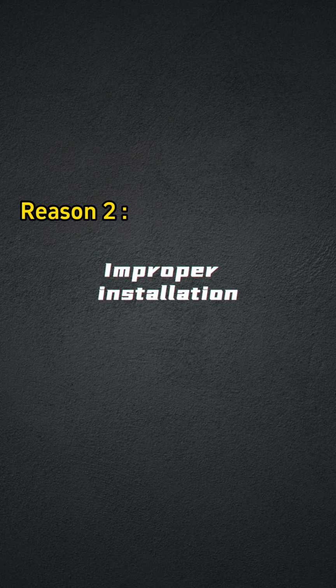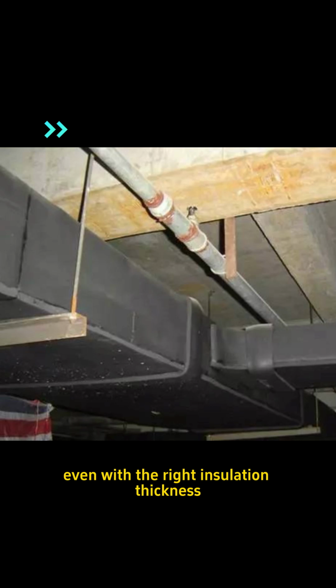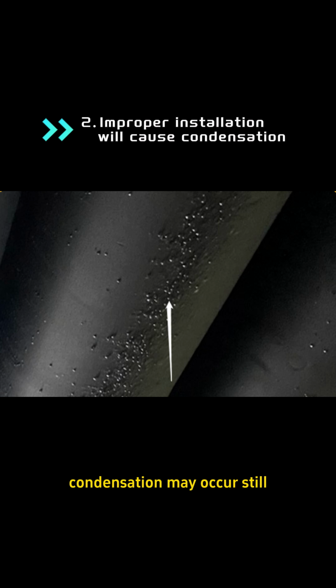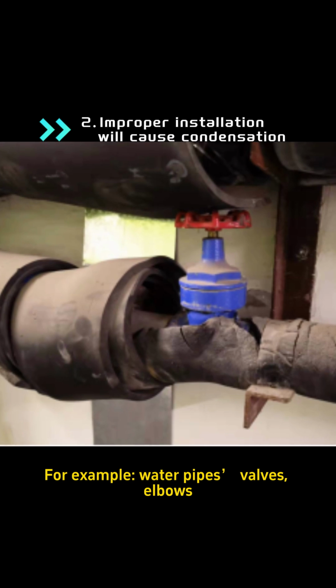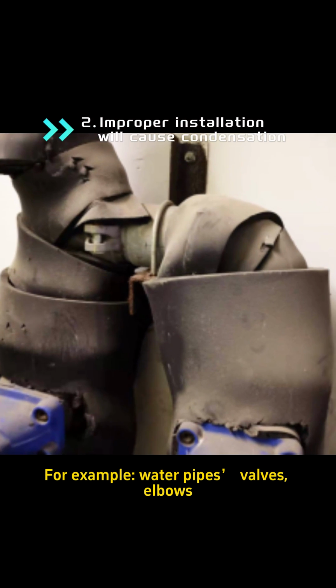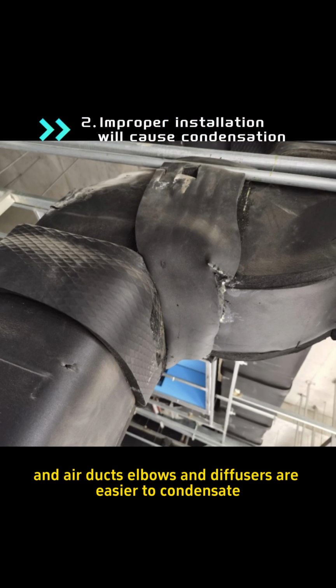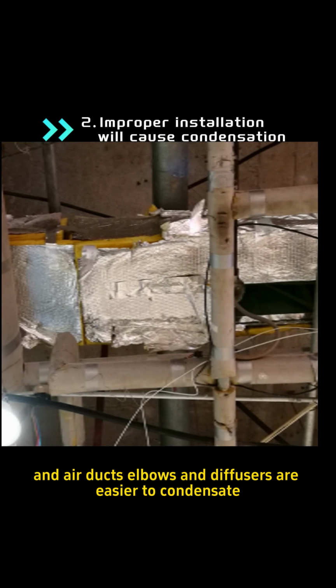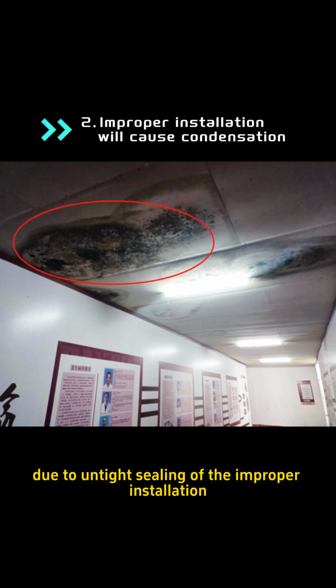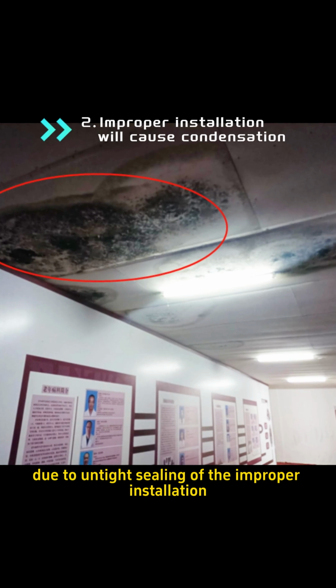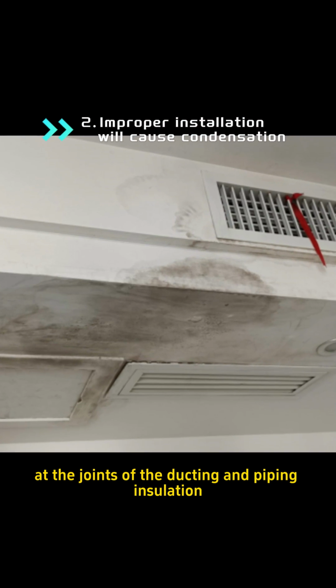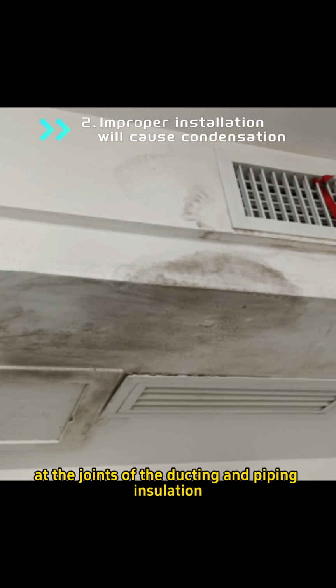Reason 2. Improper installation. Even with the right insulation thickness, condensation may still occur. For example, water pipe valves, elbows, and air duct elbows and diffusers are easier to condensate due to untight sealing from improper installation. Condensation will occur at the joints of the ducting and piping insulation.